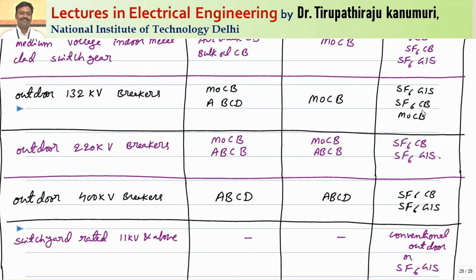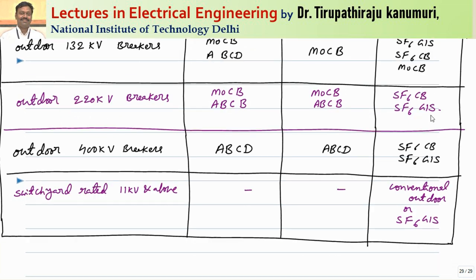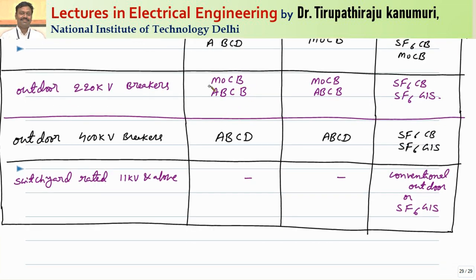For outdoor 132 kV breakers, initially minimum oil and air blast circuit breakers were used. After 1970 up to 1990, minimum oil circuit breakers were used, and after 1990 they are replaced by SF6 and minimum oil circuit breakers. For 220 kV, minimum oil or air blast were used up to the 1990s, but after that they are completely replaced by SF6 circuit breakers. For outdoor 400 kV breakers, air blast was previously used and is now replaced by SF6 circuit breakers, either simple SF6 or SF6 gas insulated substations.